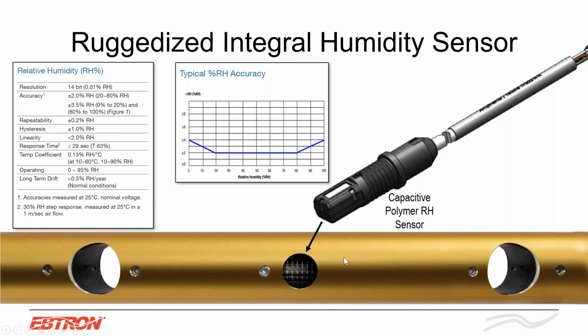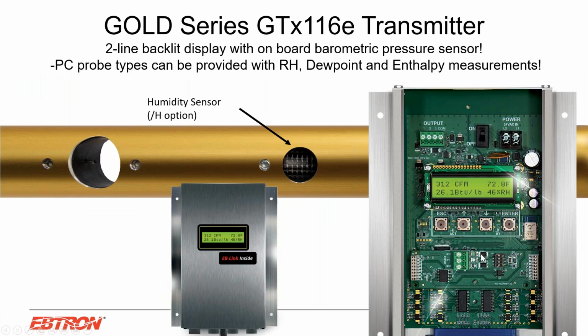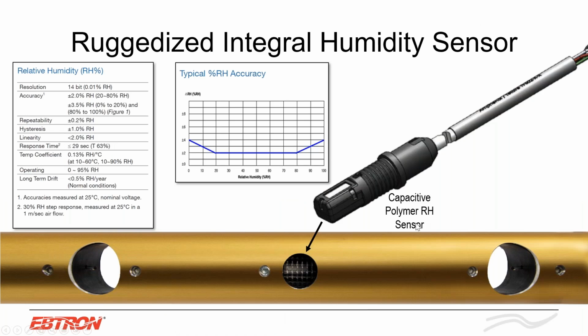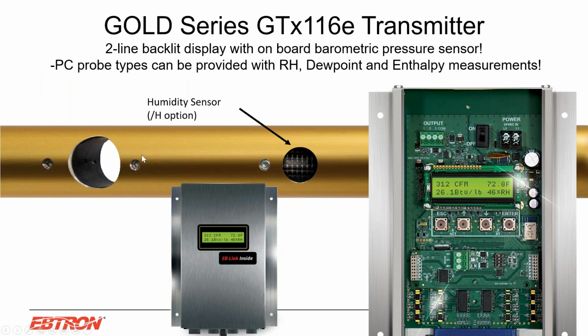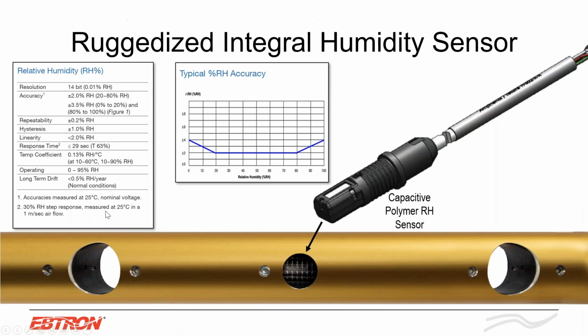Now, all relative humidity sensors drift. So what we've done is, in our menu structure here, if you ever want to recalibrate the humidity sensor, you don't have to pull this out. You can simply calibrate it to a reference device of plus or minus 10% RH right here in our transmitter menu structure. Now, again, I mentioned all relative humidity sensors drift. Well, with the thermal devices though, airflow measurement or temperature measurement, that does not drift over time. So once you install this in our reading airflow, basically set it and forget it, no drift.